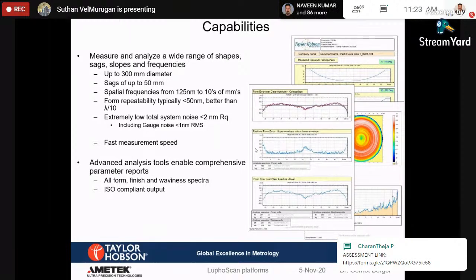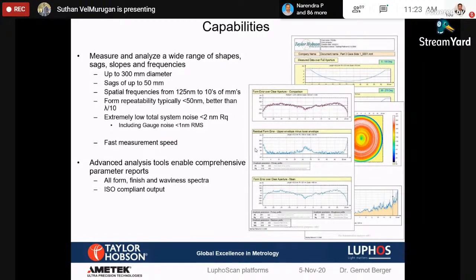But the 2 nanometer error is a cumulative of mechanical, electrical, electronics, whatever error, any form of error generated from the machine. It should not be more than 2 nanometers at any point of time. So we have masters to prove it. It will be proved during the installation of the machine. We have an internationally traceable master to prove these kinds of accuracies. Yeah. And anyway, it is an ISO compliant output.